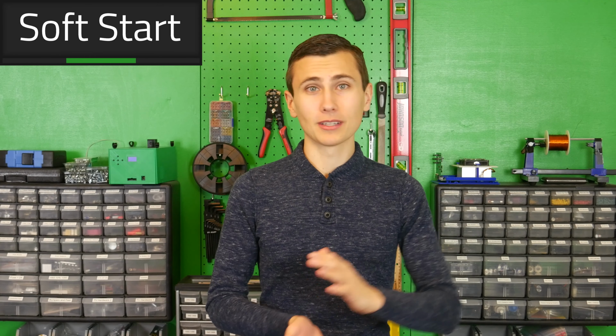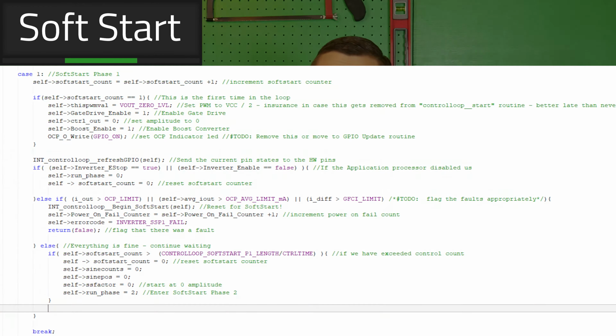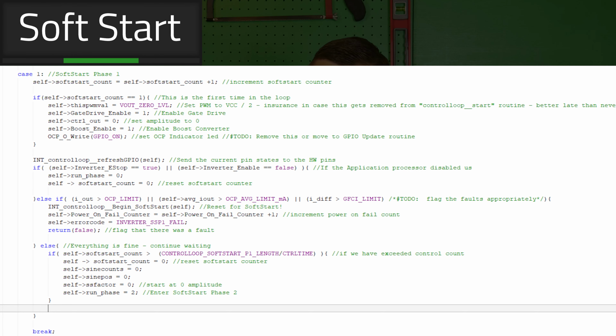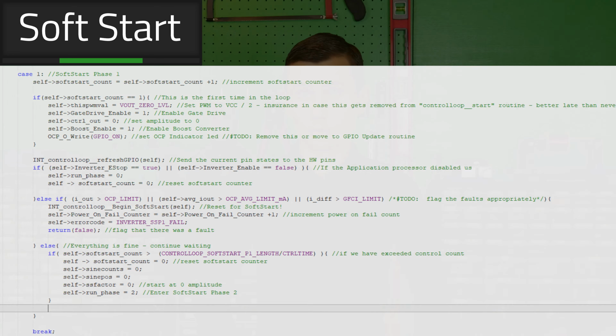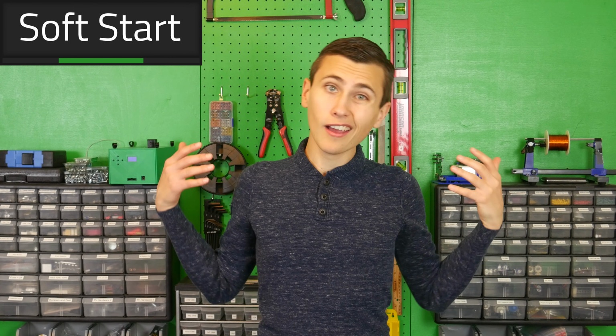Push that power button again, and things start to get interesting. Buzzing starts, things come to life, but most importantly, we enable the DC to DC boost converter and fix both inverter outputs to 50% duty cycle. This brings both legs of our UPS up to approximately 125 volts DC, and the voltage across them to approximately 0. Once here, we dwell for about a second, monitoring the leakage current, verifying that there's no excessive current draw from either leg to ground. Any current drawn now would be pretty weird and a serious fault, because there's no voltage across the output. That's 1 out of 3 safety checks.